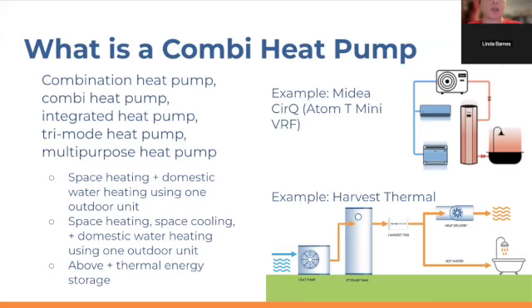Some of the combi heat pumps can do space heating, space cooling, and domestic hot water heating. And then some of those that can do all three modes can also do heat recovery, so that when you're doing space cooling and domestic hot water at the same time, the system can recover some of the waste heat from space cooling. And then many combi heat pumps also can utilize thermal energy storage.